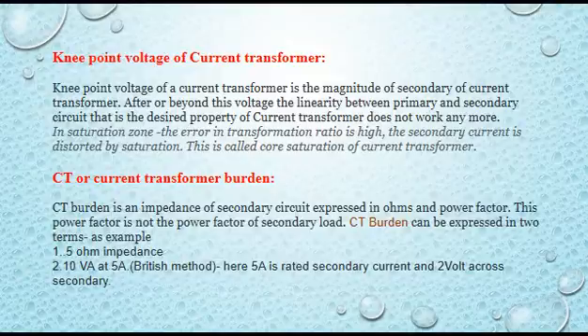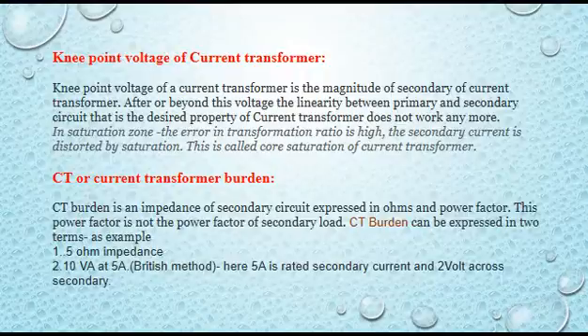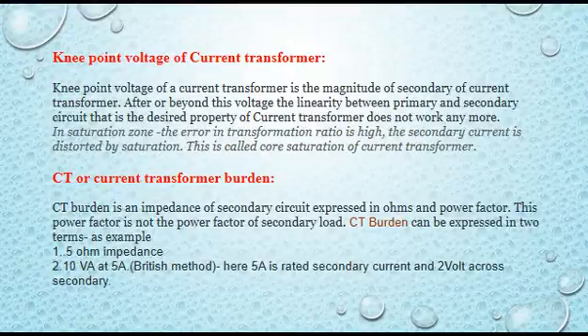In simple terms, the knee point voltage of a current transformer is the magnitude of the secondary voltage beyond which the linearity between the primary and secondary circuit — the desired property of a CT — no longer holds. In the saturation zone, the transformation ratio error is high and the secondary current is distorted by saturation. This is called core saturation of a current transformer.